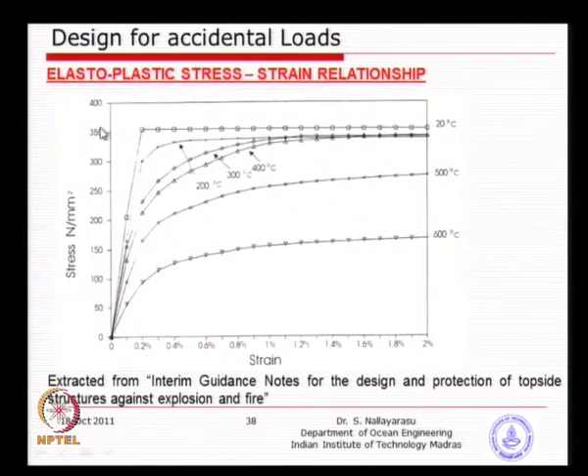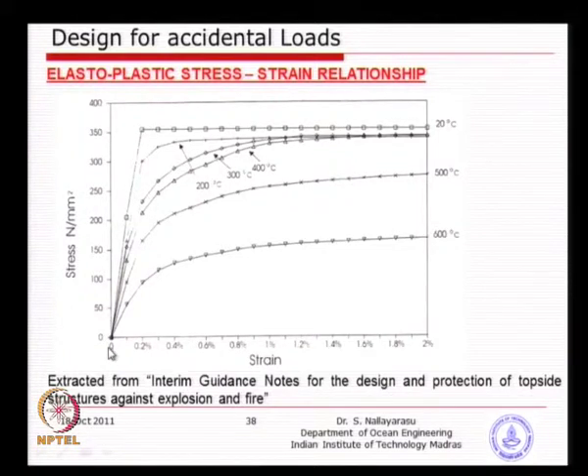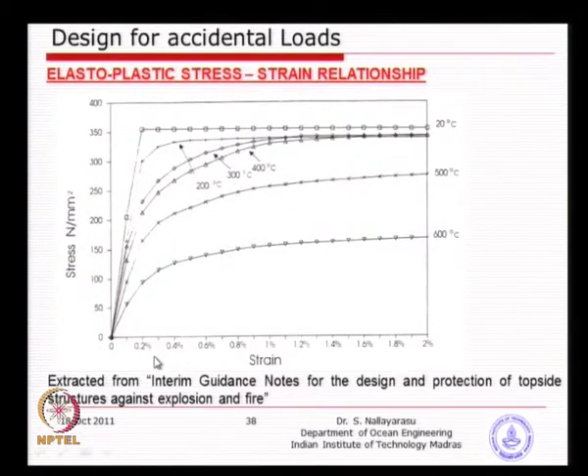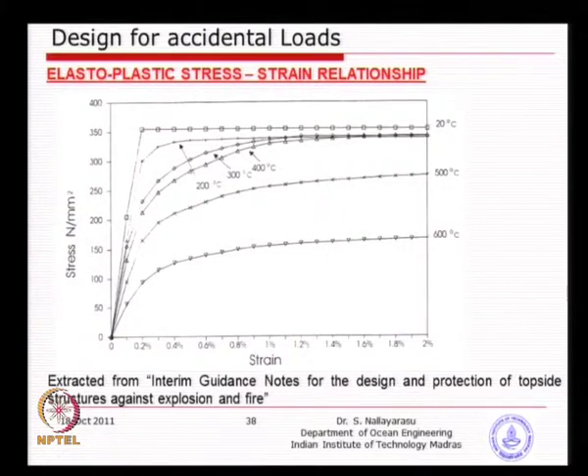When designing at say 500 degrees, you need to consider not only yield strength but also the initial modulus or tangent modulus depending on the strain level. At 0.2 percent strain at 500 degrees, the yield strength is around 160–170 MPa. But if you allow 1 percent strain, you can utilize up to about 240 MPa. It all depends on what strain you are allowing, which corresponds to the deformation you permit.